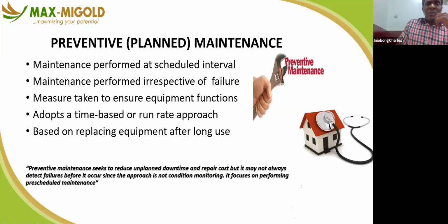Now, preventive or planned maintenance is performed at a scheduled interval. You need to draw up your schedule so that at a particular interval there are activities you need to do on that asset. For example, your generator: there are two ways you maintain it, either by run time, the run hours, or you place it on maybe a monthly or quarterly schedule, depending on the failure mode and what you have put down to do. So it's about schedule, the preventive maintenance plan is about schedule.